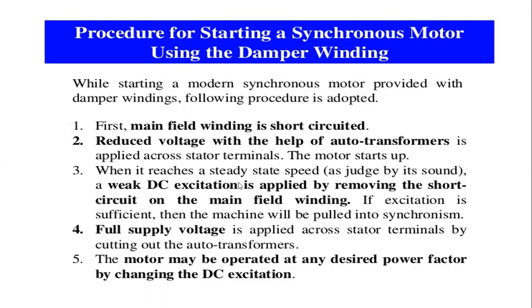When it reaches a steady state speed, as judged by its sound, a weak DC excitation is applied by removing the short circuit on the main field winding.